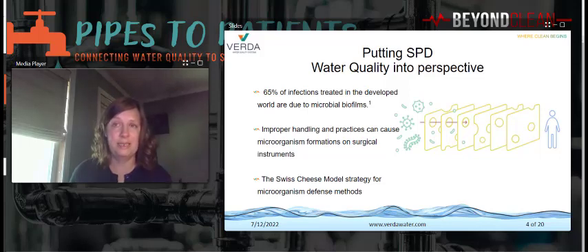Another is incomplete cleaning, which can leave lubricants and particles such as surgical soil, lint, hair, fibers, and glove powder on surgical instruments and inhibit cleaning. Also, too much time between the use and the reprocessing of the instruments can result in biofilm formation. Poor rinsing techniques can leave behind particles, soil, or detergents on medical devices. Poor quality rinse water can leave behind so many microorganisms that decontamination and sterilization doesn't remove enough of them to ensure that they're safe.